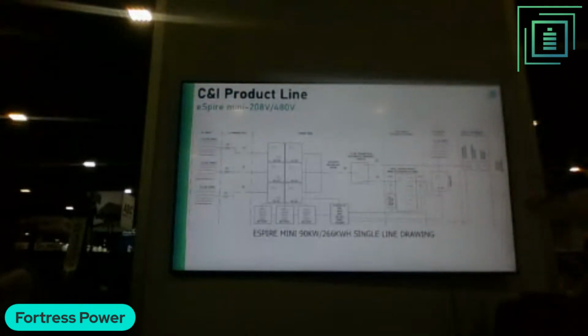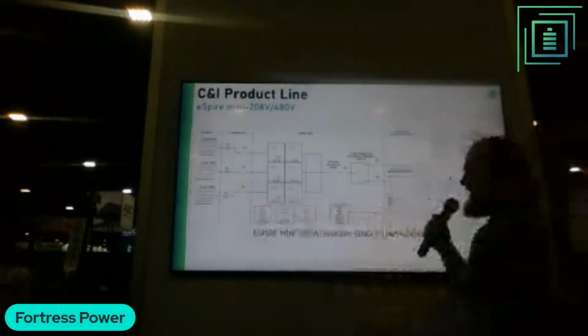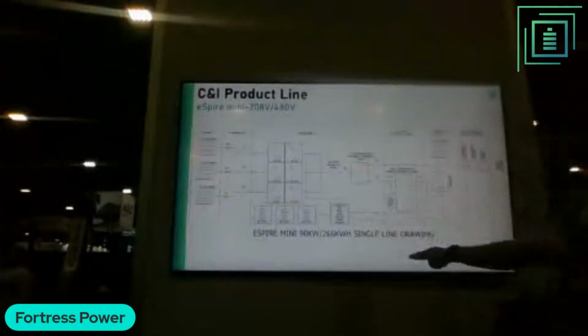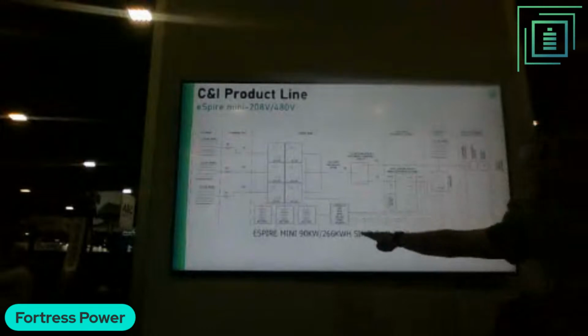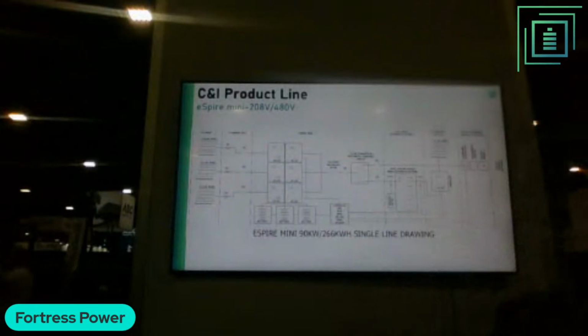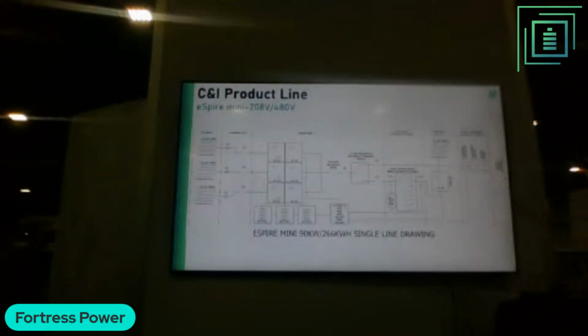So you have your grid power here. Everything between these dotted lines is inside the eSpire mini unit: the controls, the UPS, battery management system, an SEL 851 grid sensing relay that can tell when the grid goes down and sends a signal to this islanding contactor to open and island the system. All of this comes from Fortress Power. You don't have to go to a third party for your balance of system - everything you need for the microgrid is in one box from one company.